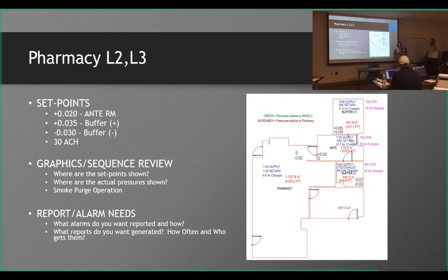If you guys are having some issues with some of these little pressurized rooms, you need some leakage in them. If they're really sealed up really tight, what we ended up doing with these doors, we cranked up those seals on the sweeps on the door, just cranked them all the way up so that it could leak underneath the door. That helps us balance out.